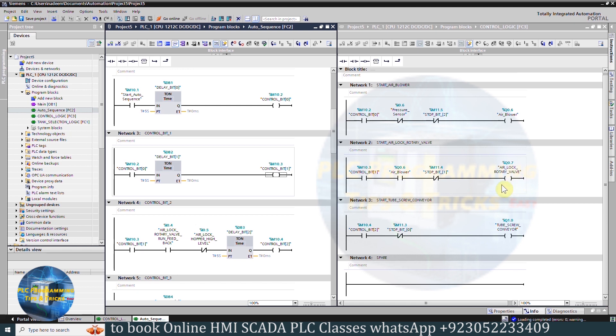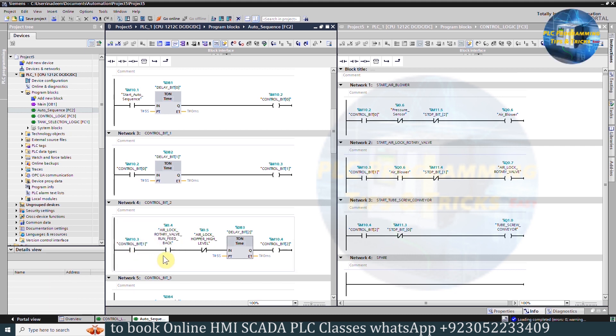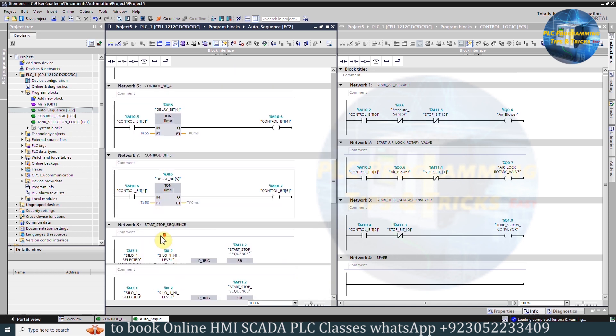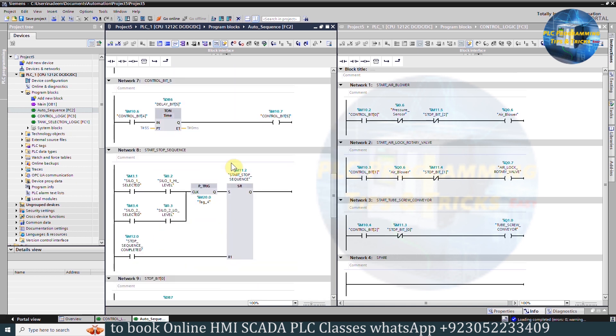Coming back to the auto-sequence function, as control bit 1 turns on, in Network 4 with the airlock run feedback I0.4 and airlock hopper not full, it will start a 5-second timer. Once this timer is over, it will turn on control bit 2 M10.4, which turns on the tube screw conveyor Q1.0. Control bits 3, 4, and 5 turn on step by step, but have not been used in the control logic.